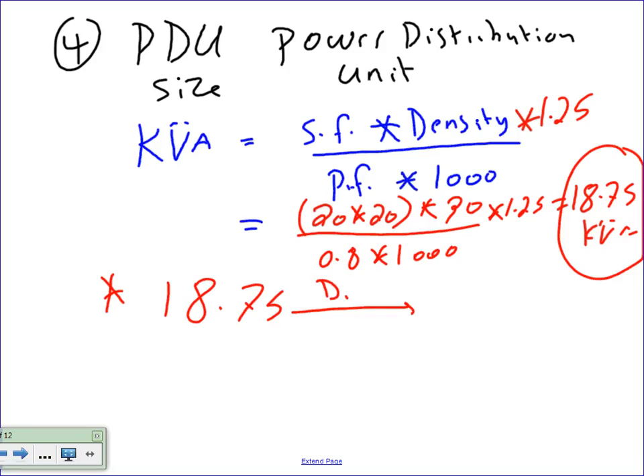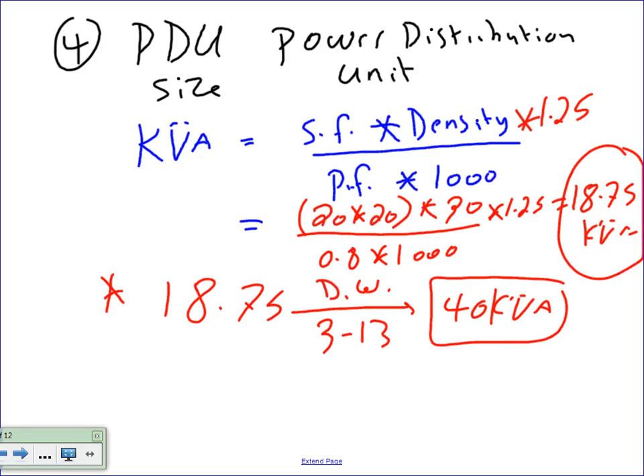Go to the table where you were supposed to have written it. What is it? 3-13. You go there, and this is where you should have put these. What's the standard? I guess it's 40, right? The same 40 kVA. So why did I repeat myself here? I'll tell you why. Because if you go to an actual manufacturer and the PDUs were different sizes, you're supposed to check with the manufacturer. Then the process will be different. So right now, for the sake of the calculation, because we're a class, these numbers are good enough, but that could be different.